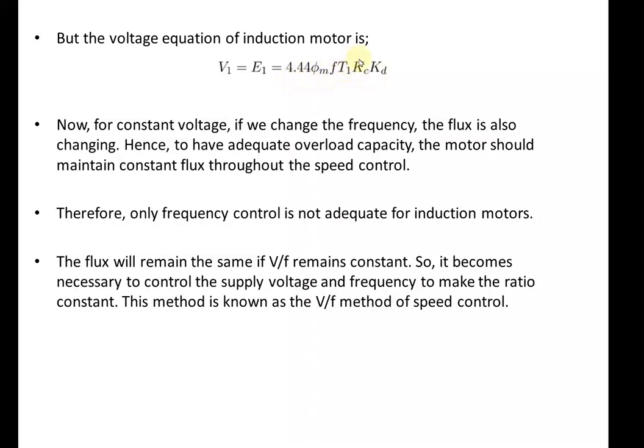In the case of constant voltage, when we change the frequency the flux is also changing. In order to maintain overload capacity, the motor should maintain constant flux throughout speed control. So only frequency control alone is not allowed, and only supply voltage control alone is also not allowed. In the V/f method, the flux will remain the same if the ratio of voltage to frequency remains constant.